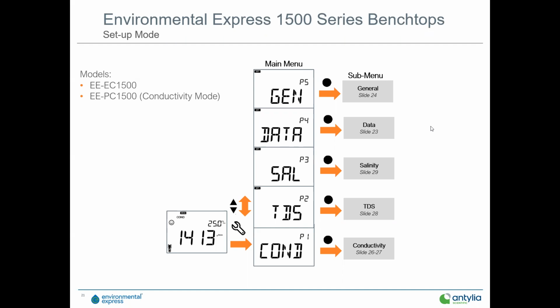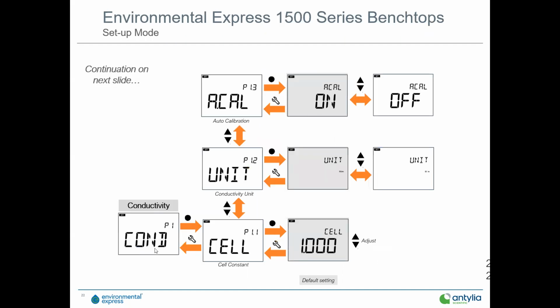Very easy to follow. So from conductivity, you push the enter button, you go into pick your cell constant. You set that up. Again, the settings button brings you right back out. You can go up and set your units. You can go up for auto calibration. Again, that auto calibration, those are the pre-programmed conductivity standards that I mentioned before, the 84 microsiemen, the 1413, the 12.88 millisiemen, and the 111.8 millisiemen standards.